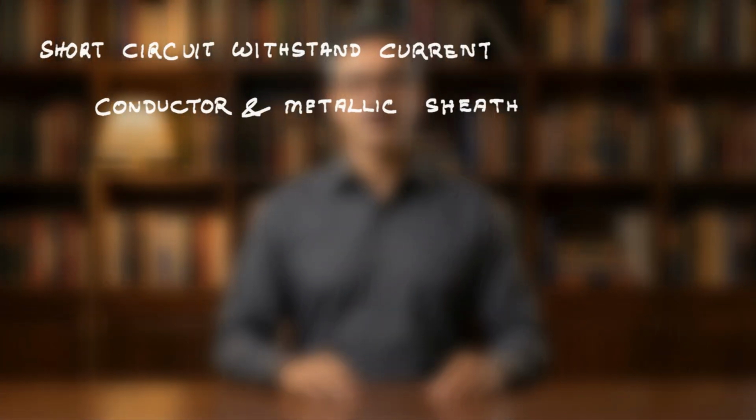In this video, we are going to discuss the necessary formulas, the logic behind those formulas, and the values of different parameters used in calculating the short circuit current level of a designed cable. Let's start our discussion now. For this, we use the most common standard, the International Electrotechnical Commission IEC 60949.